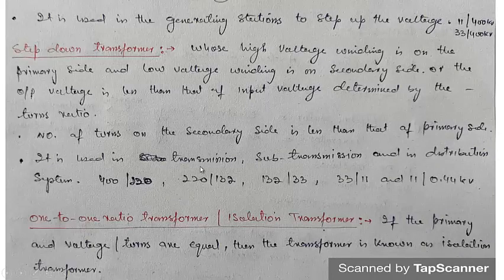It is used in transmission, sub-transmission, and in distribution. Apart from generation, we will always be using a step-down transformer. So in transmission, we may have 400 by 220 kV, 220 by 132 kV. This is the sub-transmission: we have 132 by 33 or 33 by 11. And in distribution, we have 11 by 0.44 kV or 11 kV by 230 V per phase. This is the line-to-line voltage; 230 is the phase voltage.